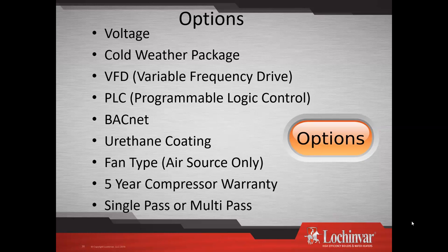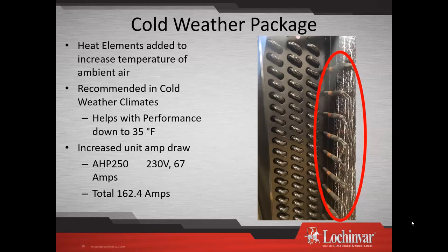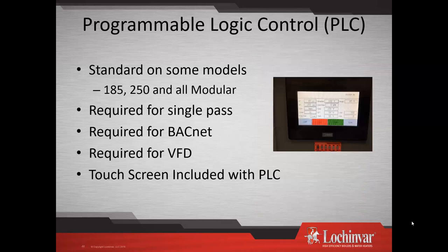So we can skip the voltage. One thing that applies to ours and many of the other manufacturers out there is to always pay attention to the details of when units are operating. Say somebody publishes that a unit will operate down to 35 degrees. We'd ask, does it have elements on it, and if so, at what temperature do those kick on? In this case you might have elements heating up your evaporator, maybe starting at 40 degrees. So maybe at 40 degrees you want to switch off and go over to your gas appliance, or just straight to a resistive element in the storage tank. There's a lot of fine detail in the new technology. We'll skip all that, standard controller.